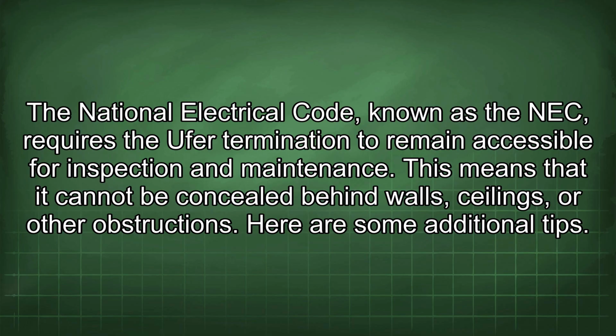The National Electrical Code, known as the NEC, requires the Ufer termination to remain accessible for inspection and maintenance. This means that it cannot be concealed behind walls, ceilings, or other obstructions.